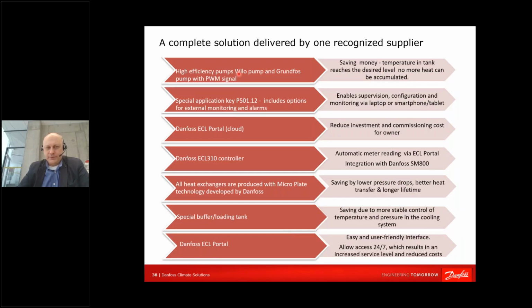We're using high efficiency pumps from leading pump suppliers with PWM signal, as I said. We're using a specific key for the application. We're using ECL Portal Cloud for the monitoring. An ECL 310 controller can be connected to other Danfoss cooling devices. Heat exchangers are produced with a microplate technology. There is a very nice seminar or webinar arranged by Mark from the Danfoss heat exchanger business unit. You can check it out. It's very useful to refresh your knowledge about heat exchangers or plate heat exchangers.